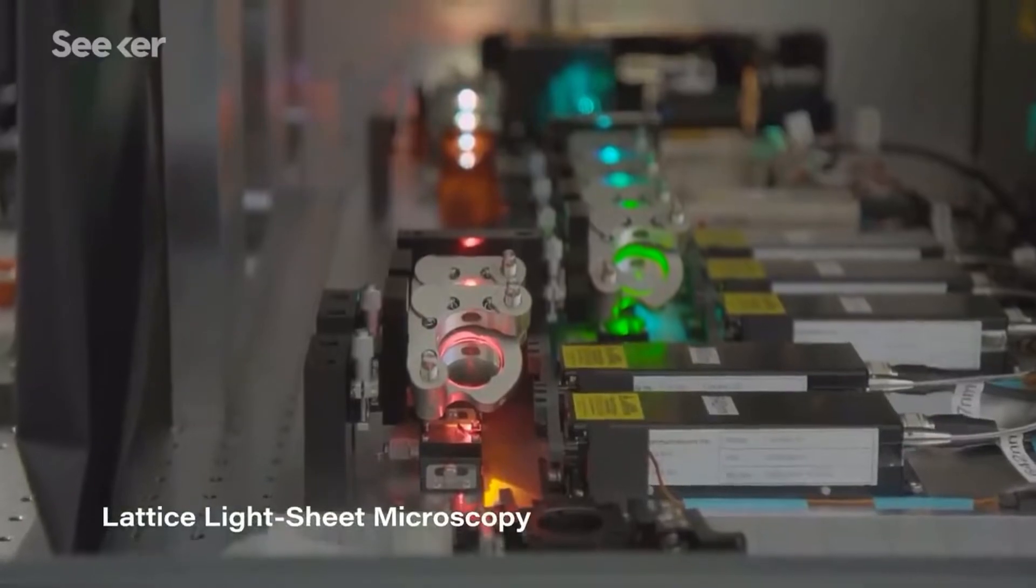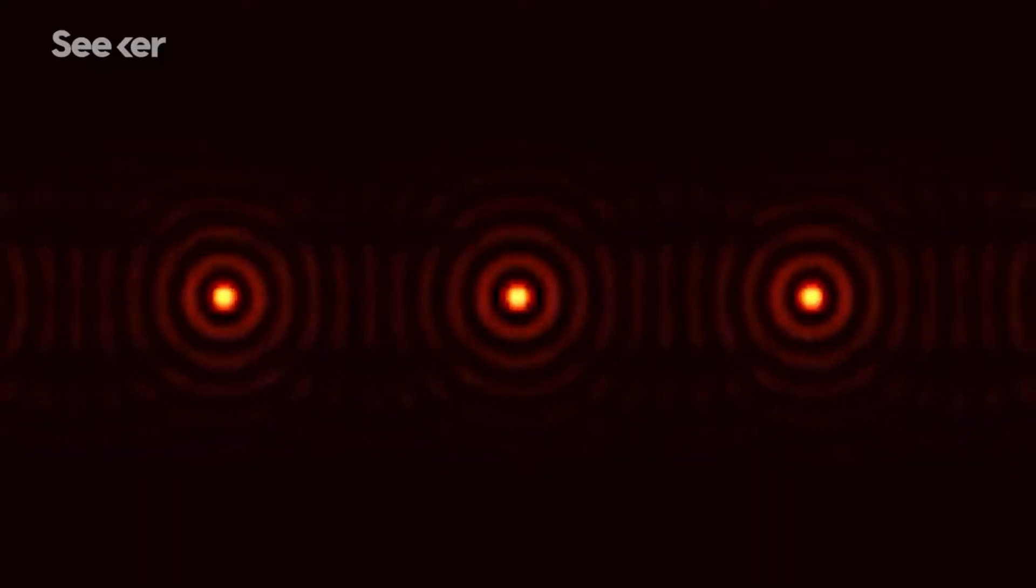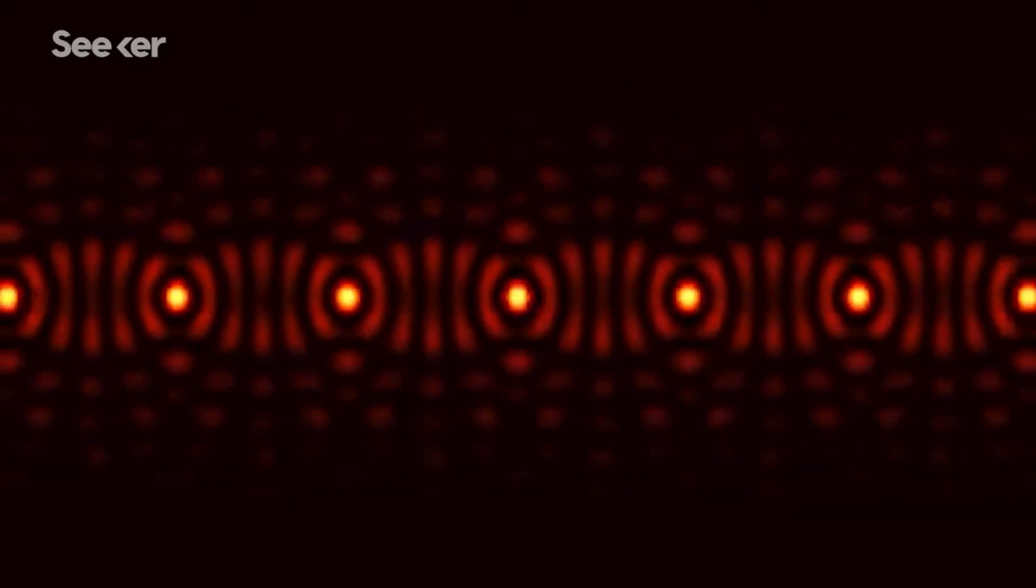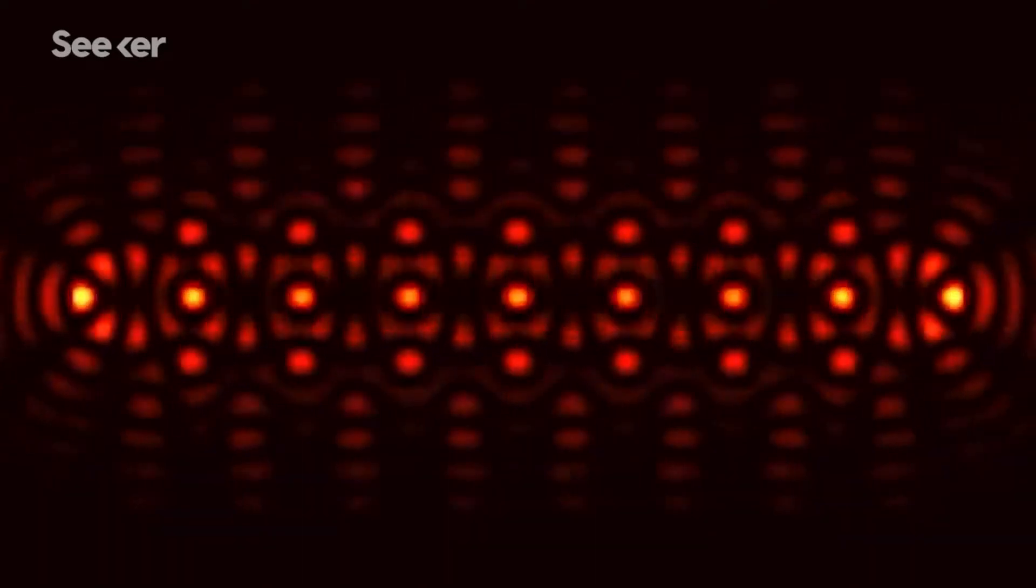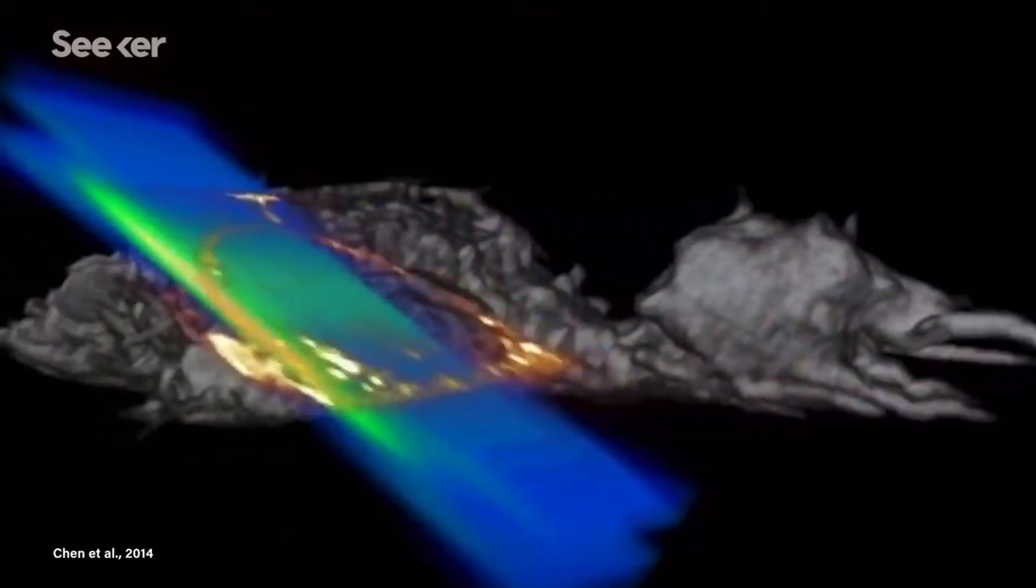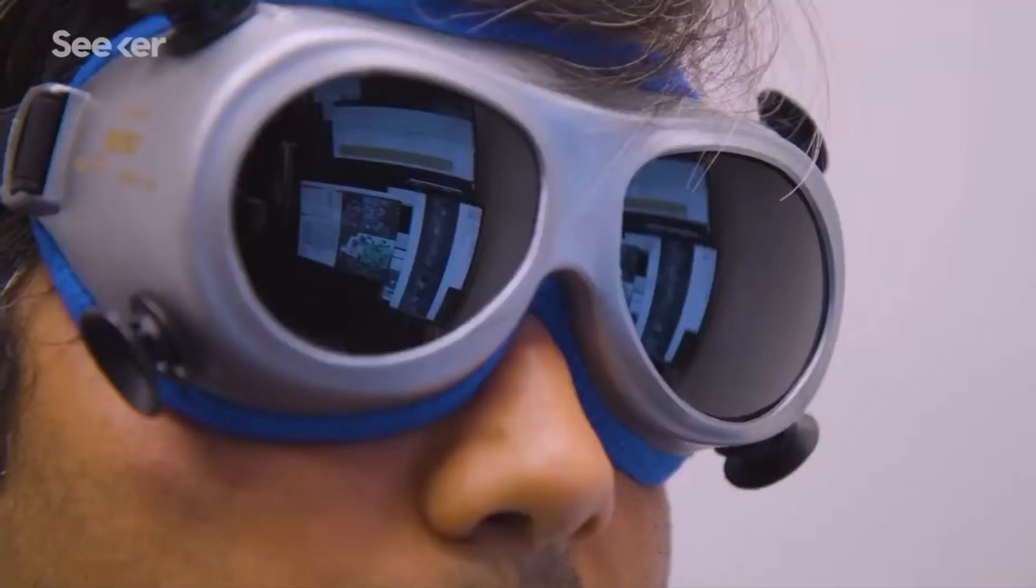Lattice light-sheet microscopy was invented a few years ago to correct for that challenge. That's a non-diffracting beam, meaning that as the beam is traversing through the sample, it's not converging or diverging. We put several of these at very specific positions such that you interfere every beam with itself and then create a very thin sheet of light. This fine sheet of light repeatedly sweeps over a sample in order to avoid the damage that's typically associated with other microscopy techniques.